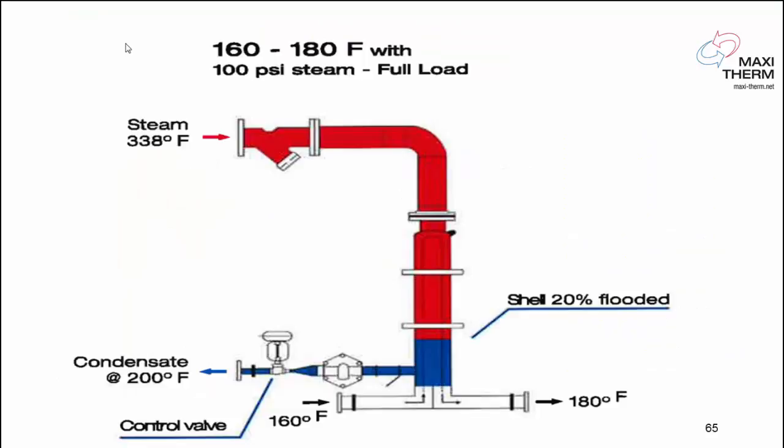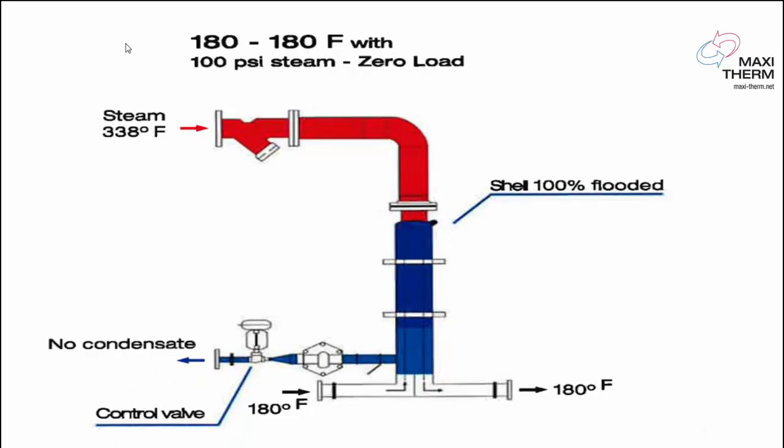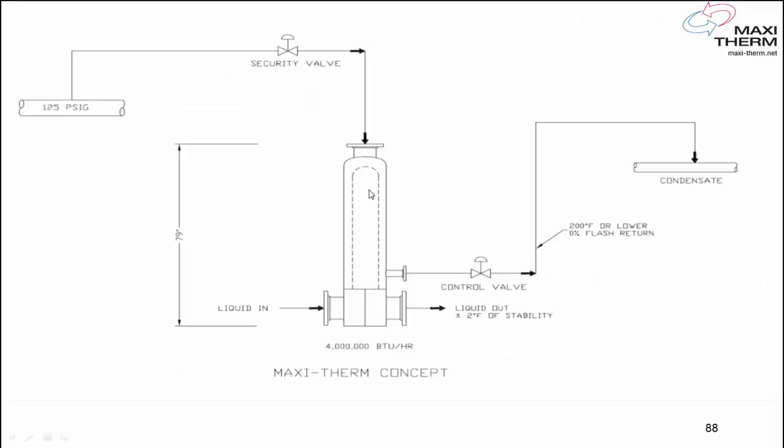This is how we modulate: at full load, 50% of the load, and 10% no load. This is a typical design for a conventional steam application — you can see your one-third/two-third pressure reducing valve station, safety valve, vent to the roof, then one-third/two-third control valve on the steam, flash tank, vent to the roof, condensate pump, and return line. Or you can do the same application the Maxi-Therm way — a very easy way to design a steam job.